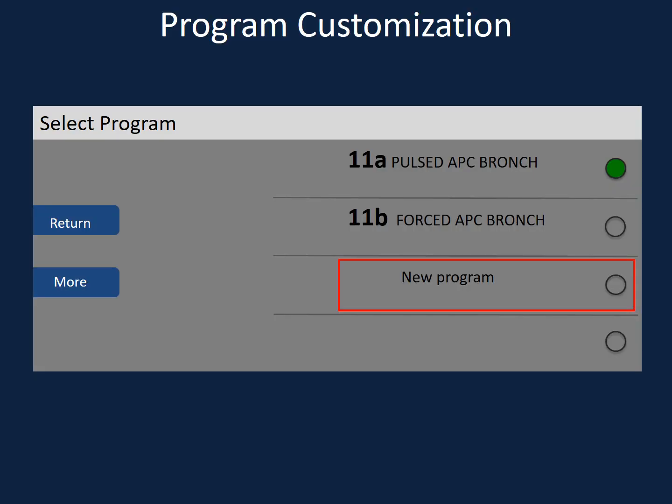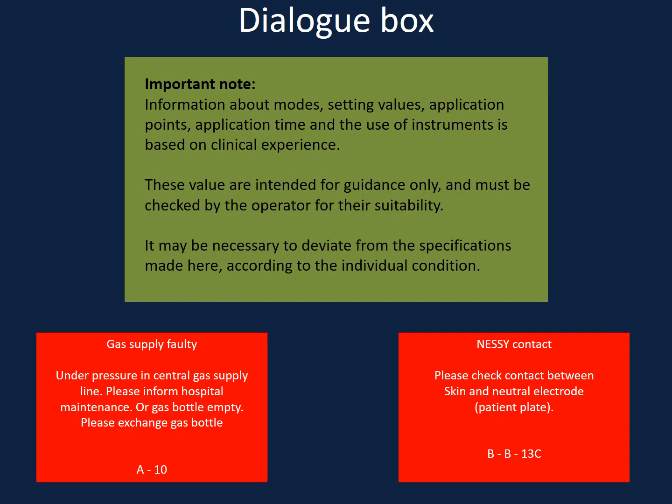The ERBE unit also offers the possibility to customize and name programs based on physician preference and the area being treated. During use, the screen may display different messages. A green dialog box conveys helpful information — for example, that the probe is being purged. A red dialog box displays critical information that impacts the completion of a function.